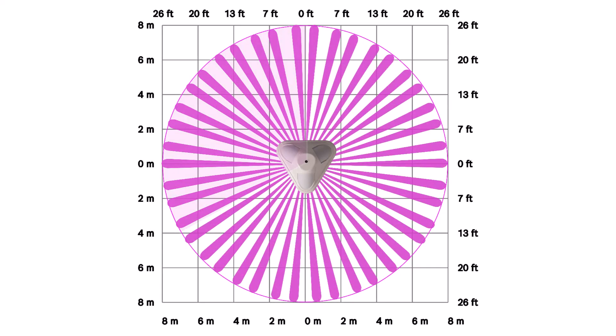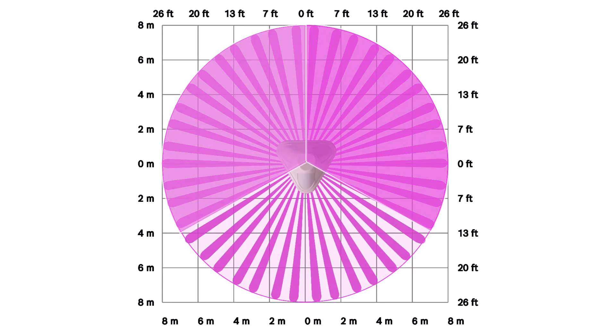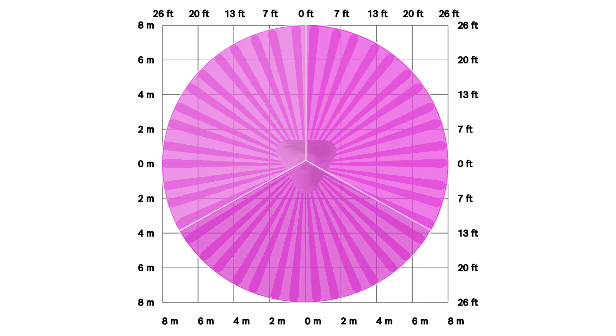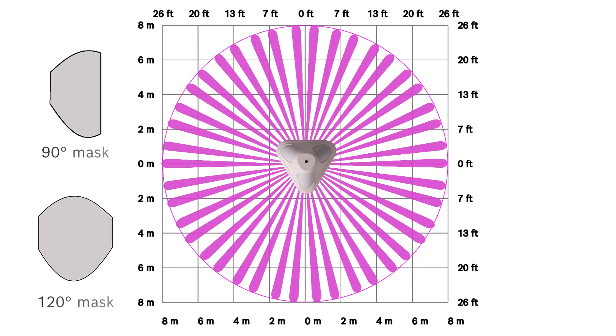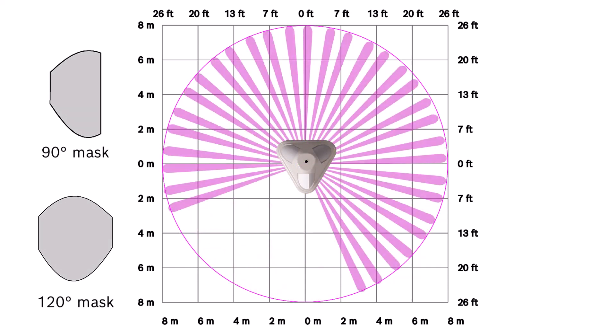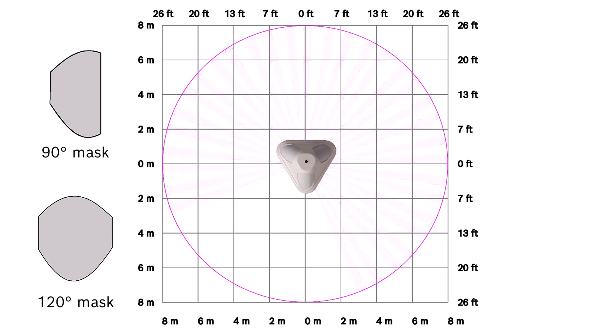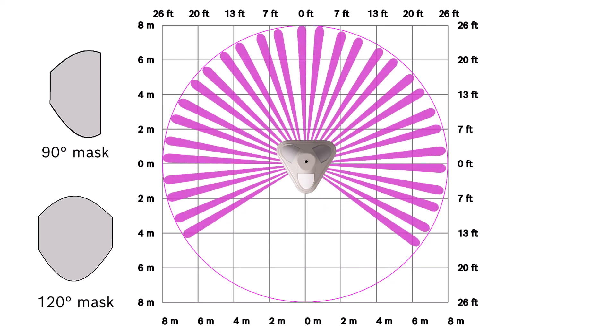The lenses split the coverage into three fully adjustable PIR zones. The coverage area can be reduced by using the masks provided. For example, here is the pattern with 90 degrees masked. Here it is with 120 degrees masked.